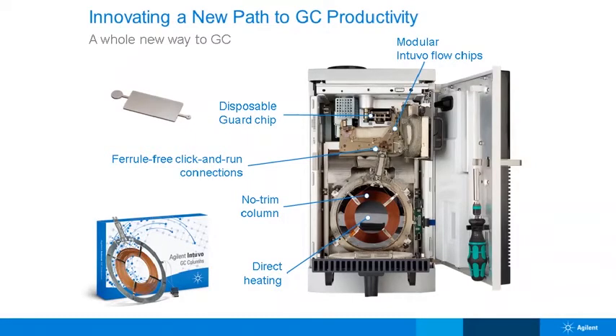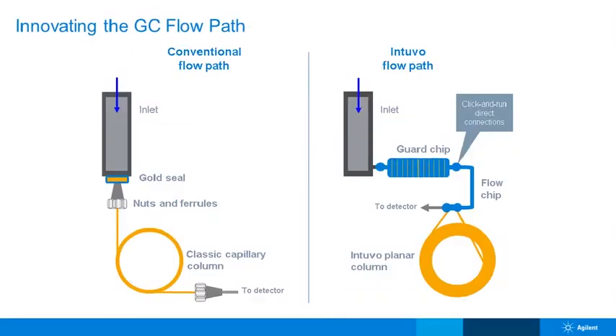So in traditional use of GC, where you have dirty matrix being injected, one classic way of handling that is to trim the column. Clearly in this situation we can't do that, but we have a disposable guard chip which has 0.8 of a meter of flow path within it. That being independently heated allows us to basically trap the matrix on that and then backflush from that. So there are some unique things still about the Intuvo that still need to be of interest here.